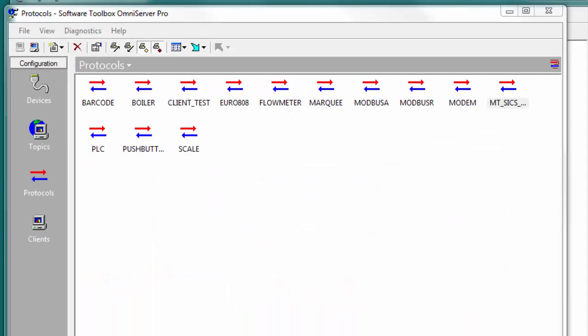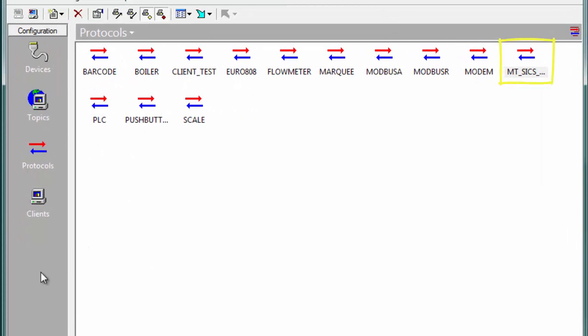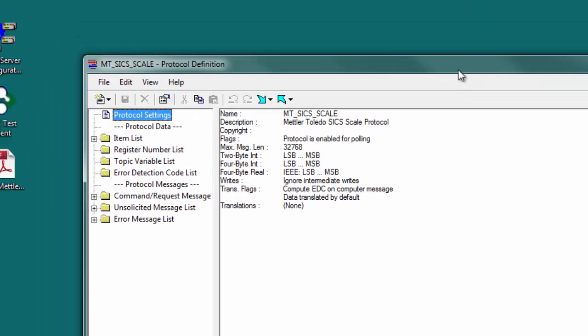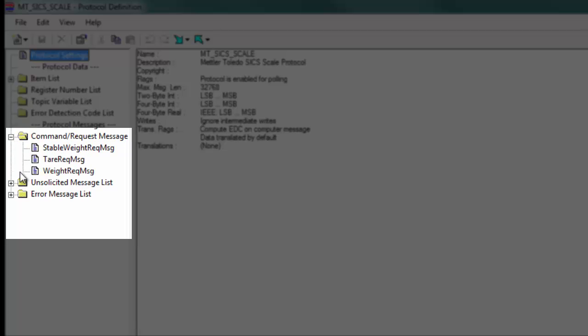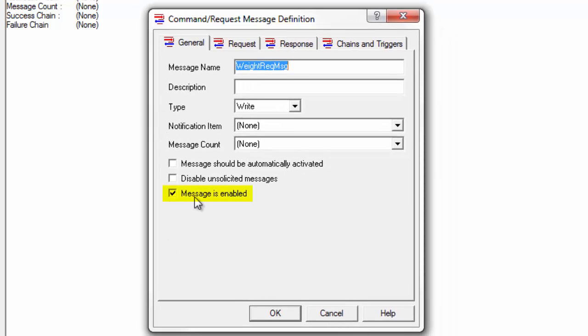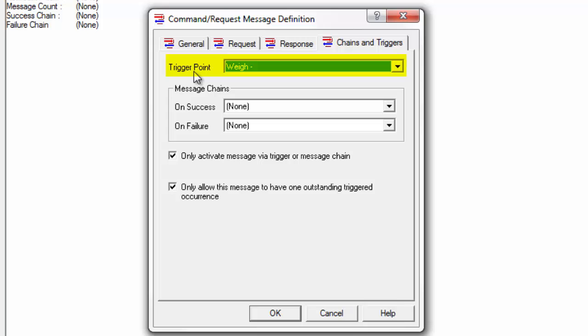I'll reduce this protocol documentation and bring up the MT SICS Scale protocol. Opening my Omni Server configuration and going to the protocol section, it's MT underscore SICS underscore scale. If I open that up and maximize it, then go to my command request message list — the command we were just looking at is the weight request message. My message is enabled, it is a write-type message because we're writing a command to the device. It's currently set up so that it can be triggered from your client application — your HMI or whatever application you need to get your weight data into. When triggering an Omni Server command, we set up a trigger item to which you write a discrete true or logical true from your client, and that causes Omni Server to send this message to your scale.